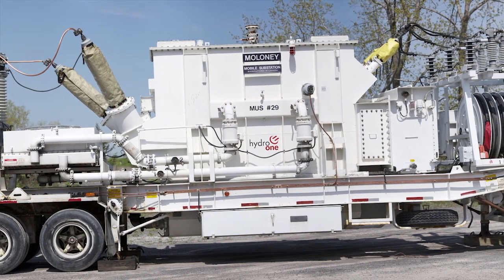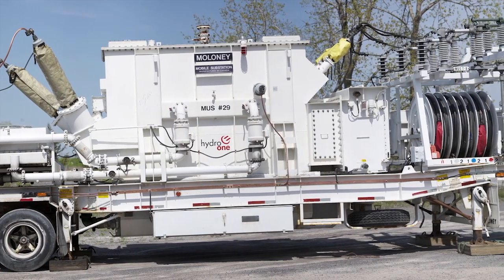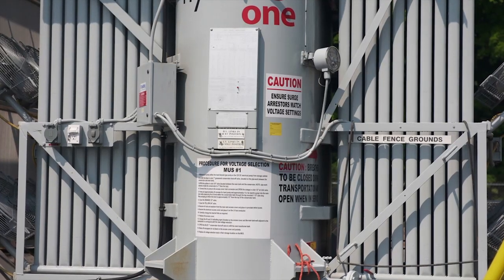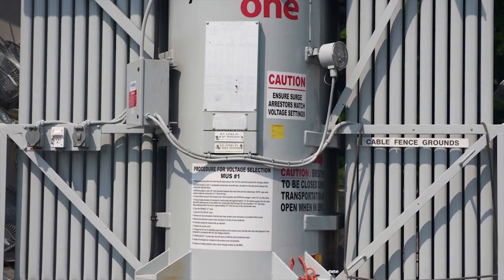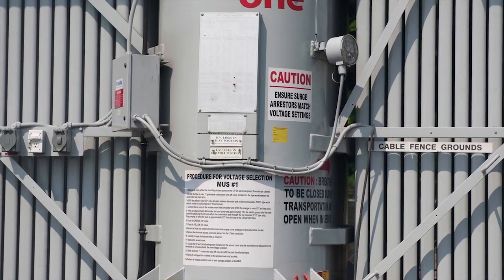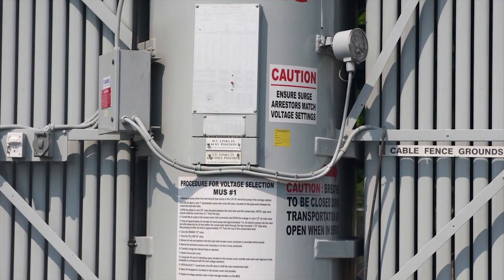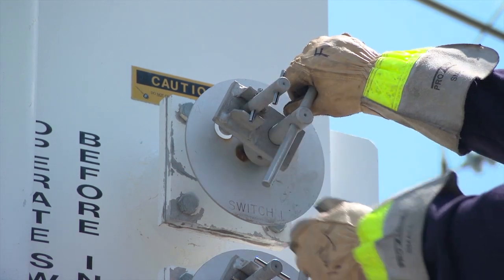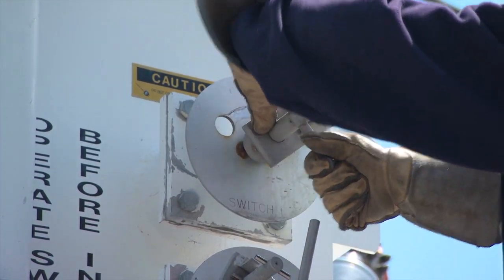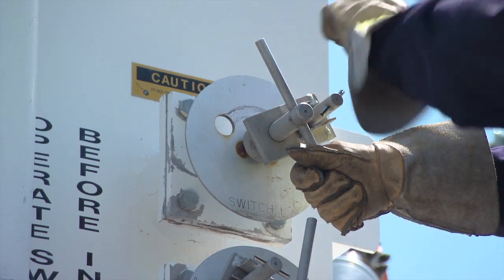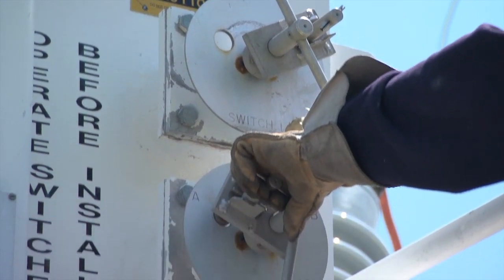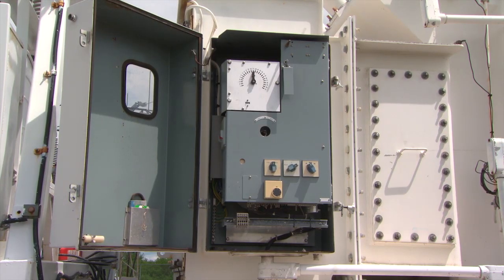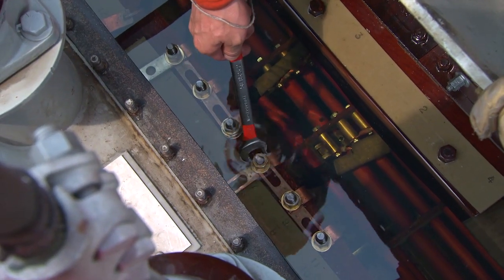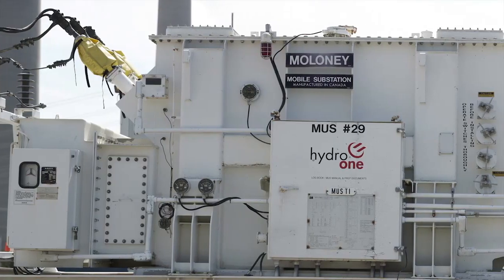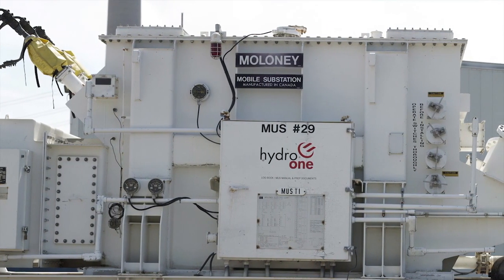MUS transformers are oil-filled and have a capacity of anywhere from 5 to 20 MVA. They can be set to different primary and secondary voltages and must be able to match the voltages at the DS. For voltage regulation, MUS transformers are equipped with either off-circuit tap changers, underload tap changers, tap links, or any combination of these. Some transformers use aluminum tanks to reduce the total weight of the unit.